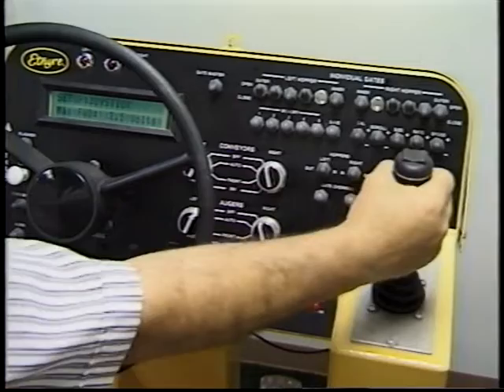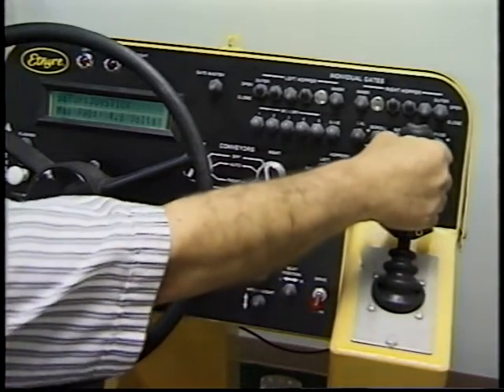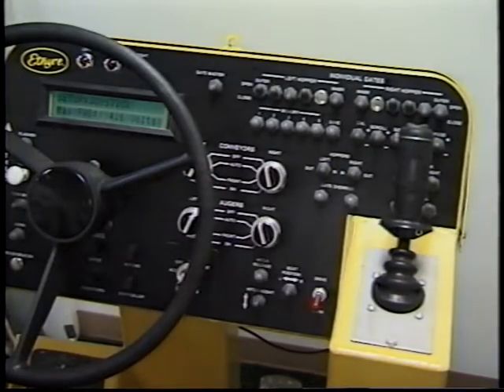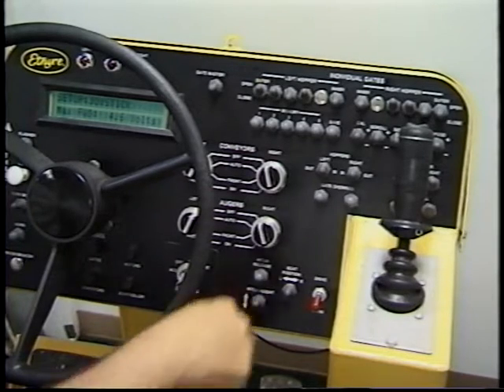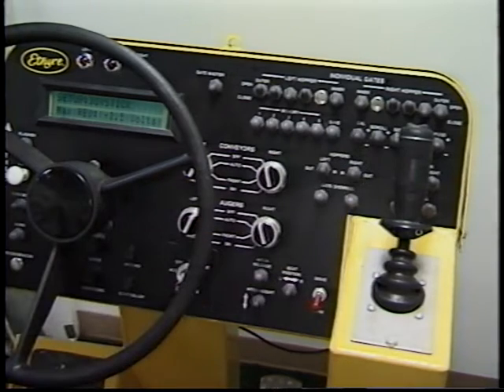Push the stick full forward. The reading should change to approximately 4.8 or 4.9 volts. When you have the stick fully forward, push the CAL switch to calibrate the full forward position of the control stick.